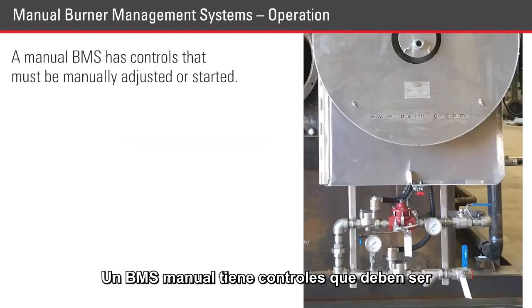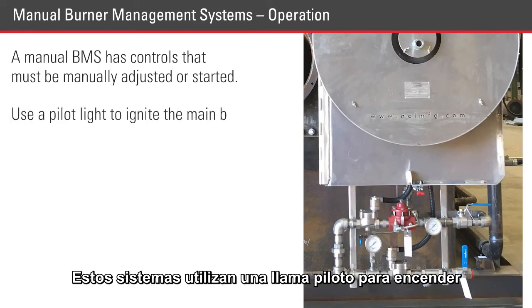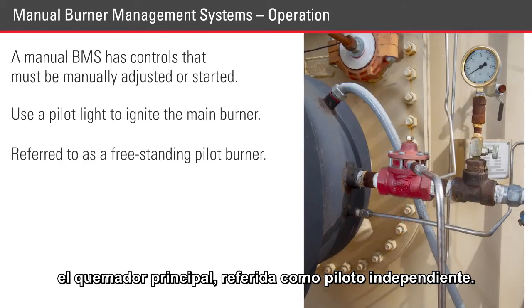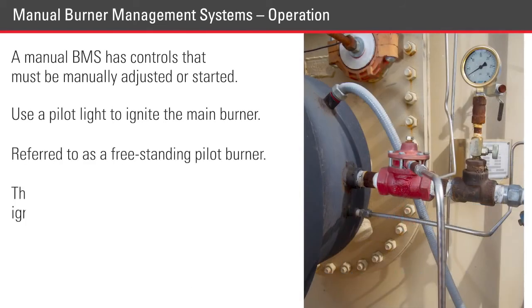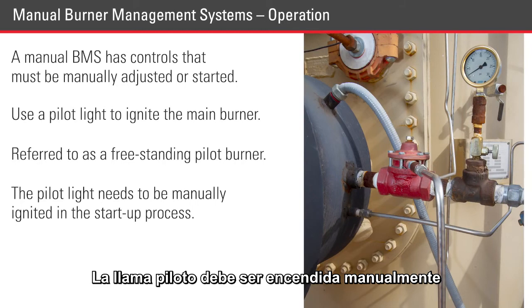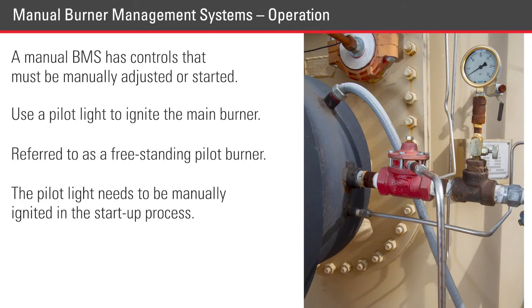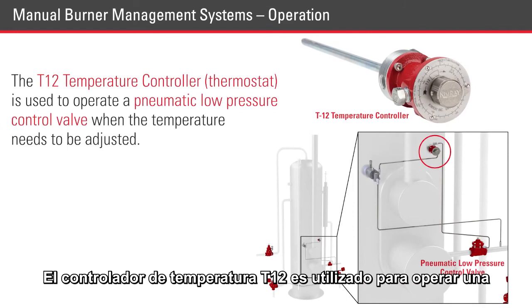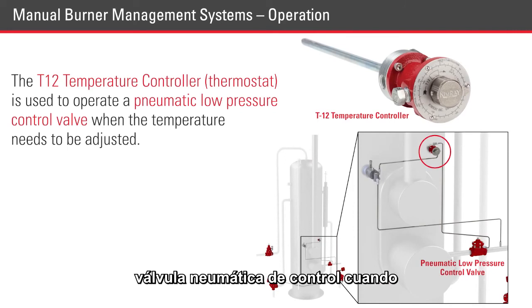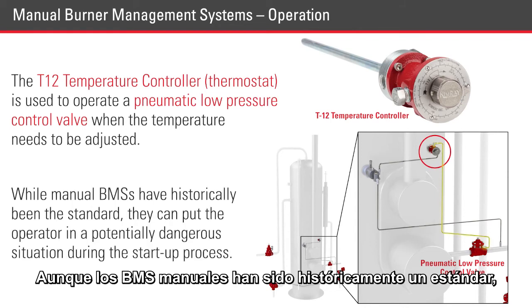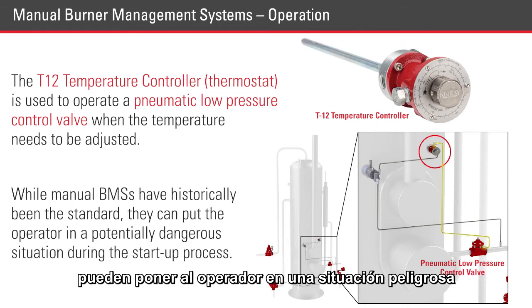A manual BMS has controls that must be manually adjusted or started. These systems can use a pilot light to ignite the main burner and are referred to as a freestanding pilot burner. The pilot light needs to be manually ignited in the startup process. The T12 temperature controller is used to operate a pneumatic low-pressure control valve when the temperature needs to be adjusted. While manual BMSs have historically been the standard, they can put the operator in a potentially dangerous situation during the startup process.